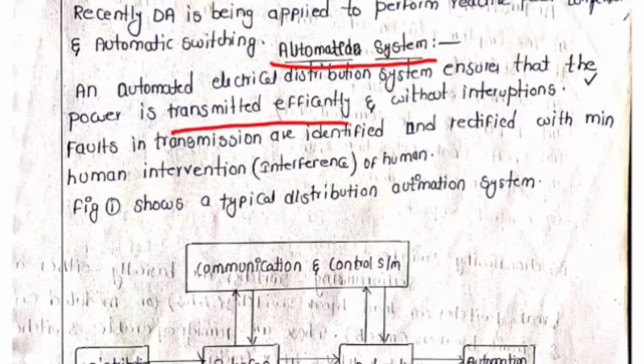Faults in transmission lines are rectified with fewer human interventions. How do we identify a fault in long transmission lines or in any substation? If any fault occurs in buses, relays, a feeder or a transformer, the fault detection system can monitor and record the fault event, whether the fault level is low or high. If it is a temporary fault, the sectionalizing switches and reclosers will automatically operate.